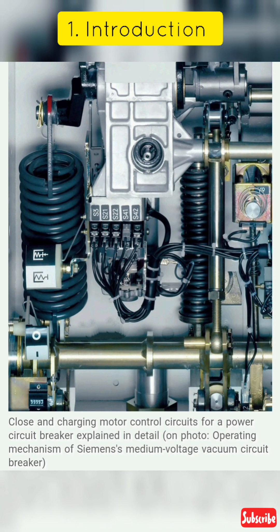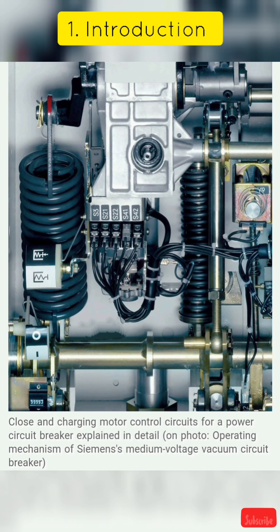Despite having numerous control circuits, all of them ultimately boil down to the CB close and trip coils. It's worth mentioning that switchgear designs must incorporate interlock systems in order to prevent unintentional closures that could compromise the security of both people and equipment.